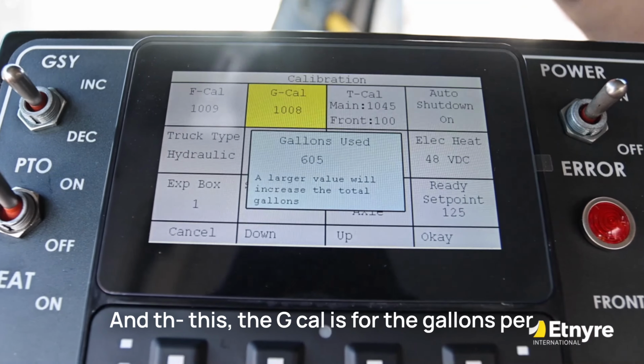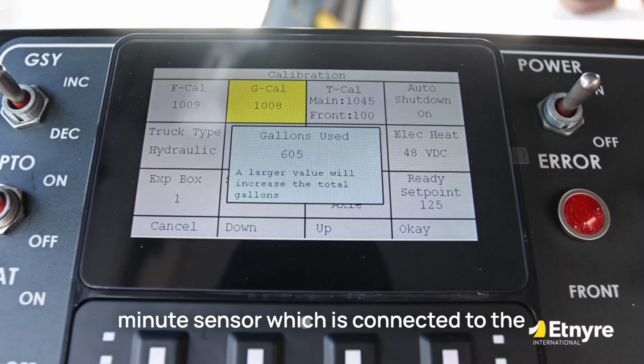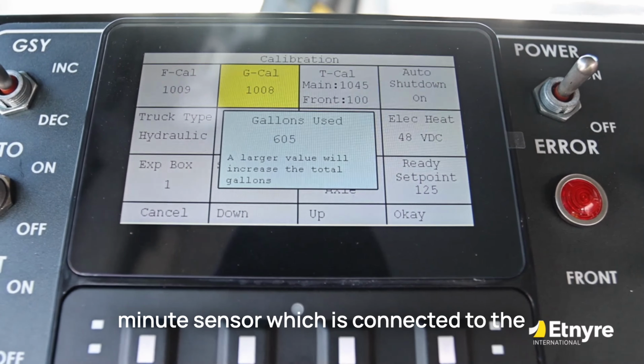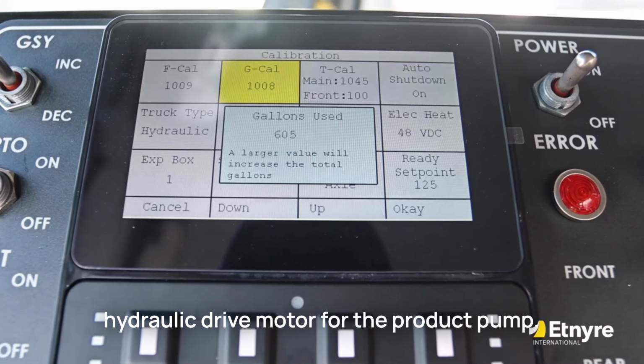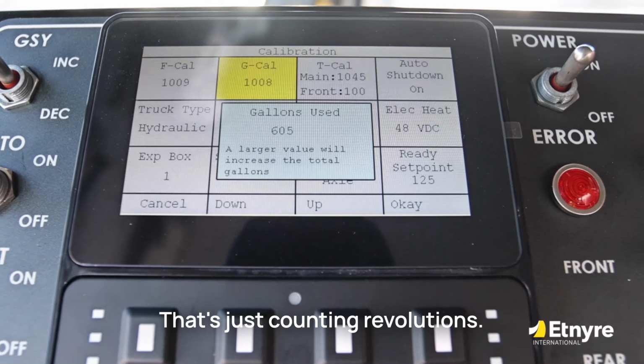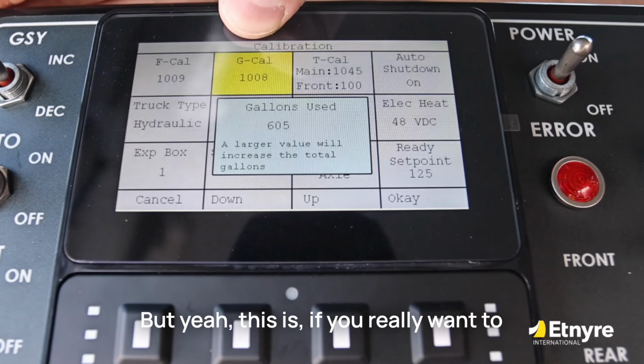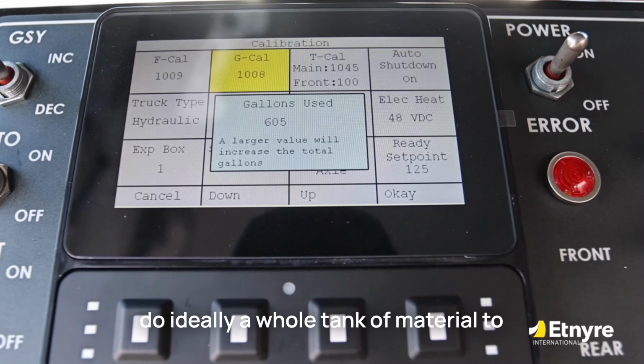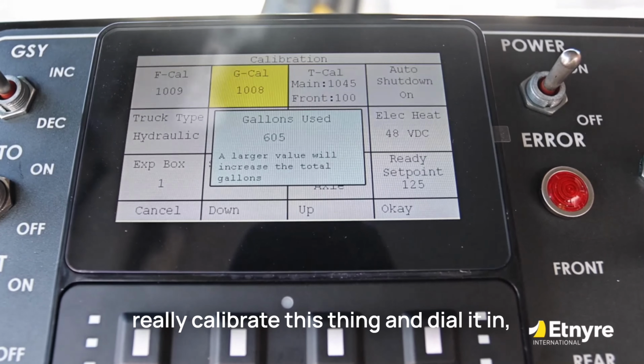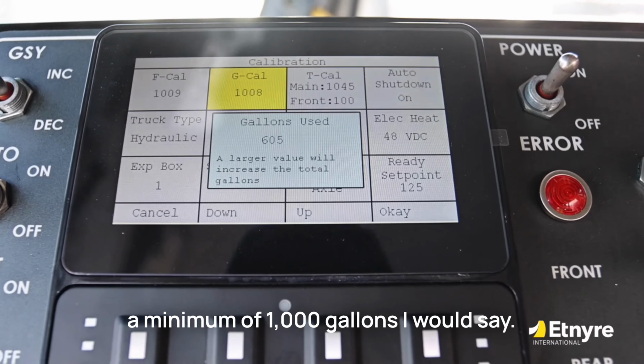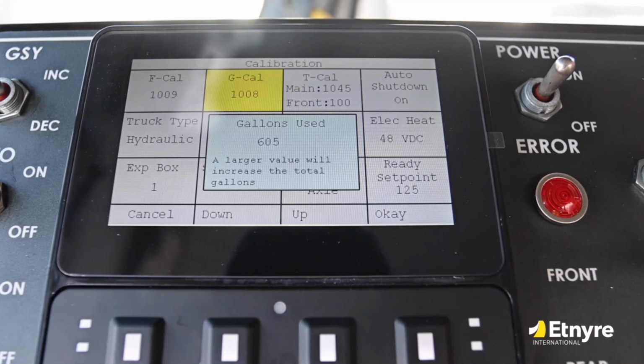And the GCal is for the gallons per minute sensor, which is connected to the hydraulic drive motor for the product pump. That's just counting revolutions. But if you really want to do it, ideally, a whole tank of material to really calibrate this thing and dial it in, a minimum of 1,000 gallons, I would say.